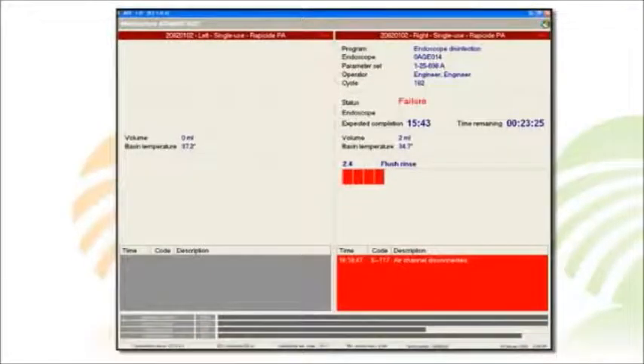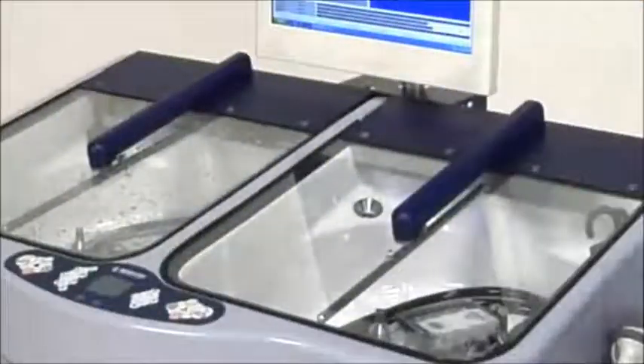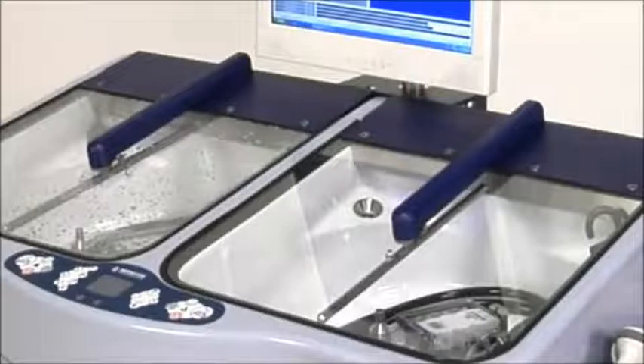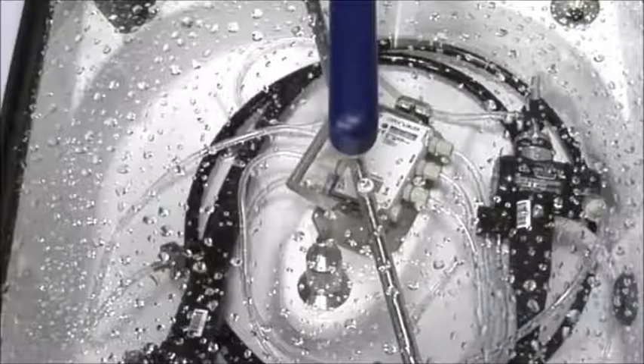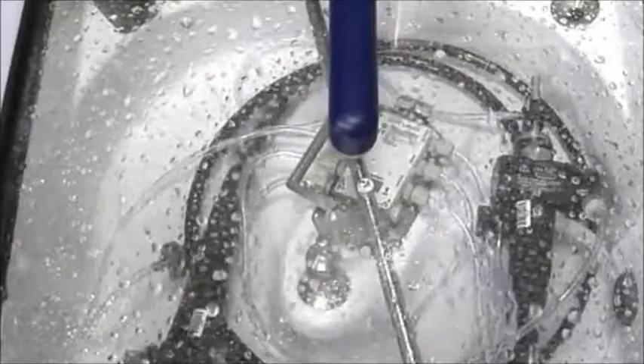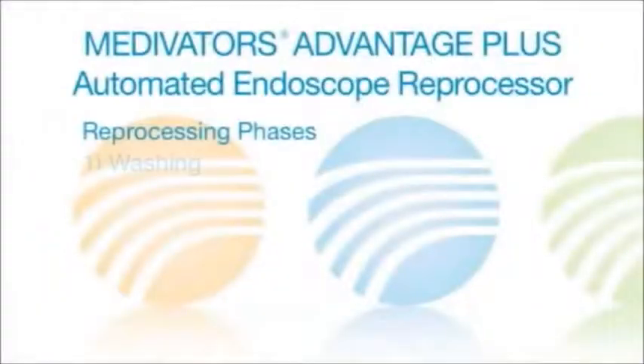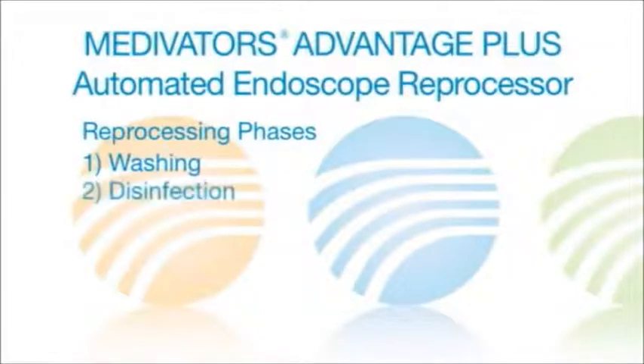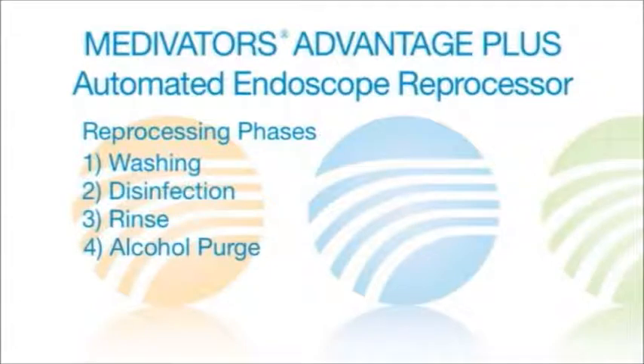If the system detects a channel disconnection or blockage, an error message will display on the program screen and the cycle is halted. The remainder of the disinfection process is fully automated. No further operator attention is required. The duration of the Advantage Plus cycle depends on the parameters that have been entered and the reprocessing phases chosen. The phases include the washing phase, disinfection phase, rinse phase, alcohol purge phase, and air purge phase.